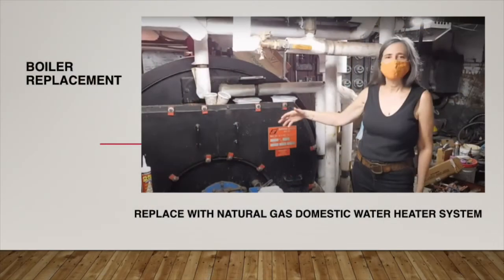Get rid of it and put a small, simple gas-fired boiler that only heats the domestic hot water. It heats cold water for the domestic hot water. We make sure it's generously sized so that nobody ever gets a cold shower and gets inspired to turn the water up. We heat it to 49C, also known as 120F for the people who use the obsolete unit system. And because we don't overheat it, the faucet parts last longer and we save a lot of energy by not overheating it.